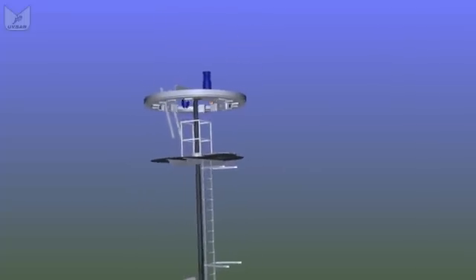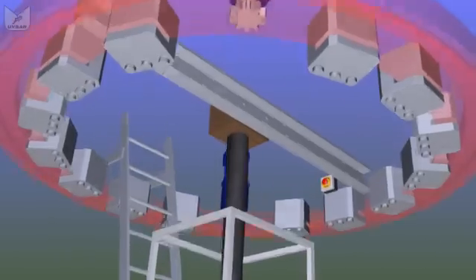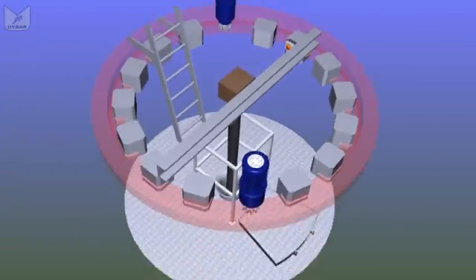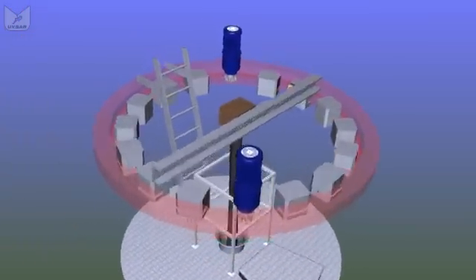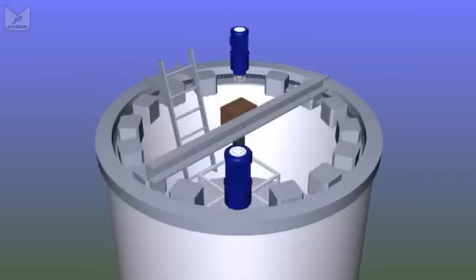And then it starts looking very much like the smaller turbine did. We have a yaw ring bolted to the underside of the nacelle, joining it to the top of the tower. Series of disc brakes run around that yaw ring to lock it in position when the wind isn't changing direction. And when it is, we have a series of either electric or hydraulic motors that rotate the entire mechanism around on the top of the tower.